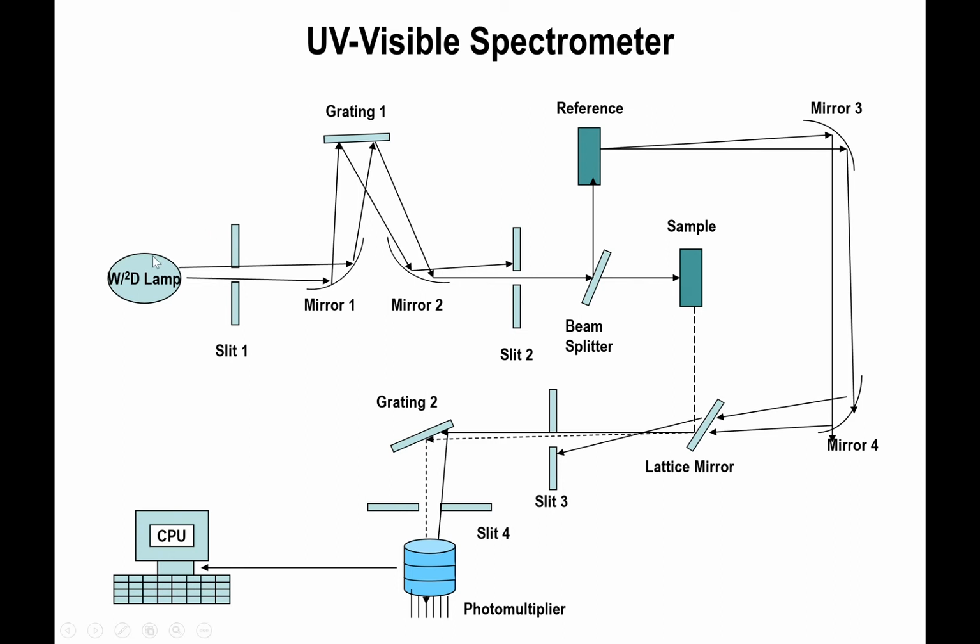But typically, you will have a lamp, which is either a tungsten lamp or deuterium lamp, or a duet of tungsten with deuterium. Tungsten ensures that you are shooting the entire visible spectrum, whereas the deuterium lamp ensures that you have ultraviolet rays of light passing through. So then what happens is that you shine the light onto a mirror that bounces the light to a grating. And the grating is mechanical, so it can actually rotate on its axis. And the beauty of the grating is that there is an angle of reflection that mathematically matches the wavelength of the light source to this angle.